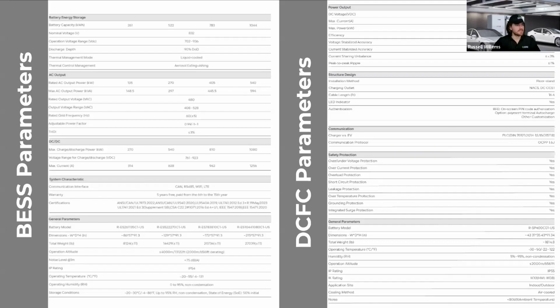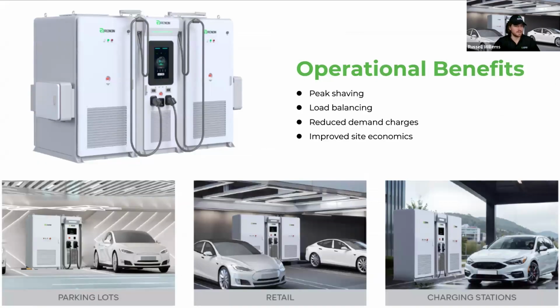To zoom back out in terms of why add a BESS solution to your DC fast chargers: peak shaving alone is a tremendous benefit. Just taking off that 50 kilowatts of demand charge that can sneak up on you when you first drop a DC fast charger—that alone can be huge savings. People are paying an additional $2,000 to $5,000 a month just in those spikes in demand charges. So if you're paying $5,000 a month, something like this could pay back easily within less than a 5 year ROI, often significantly less.